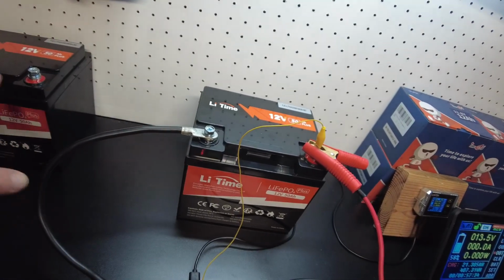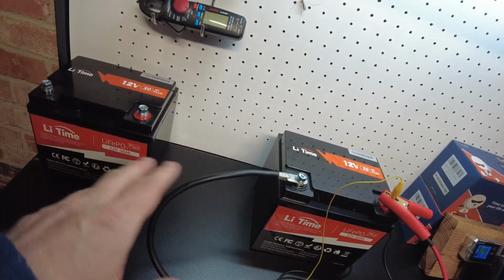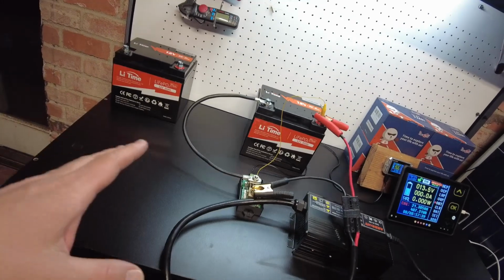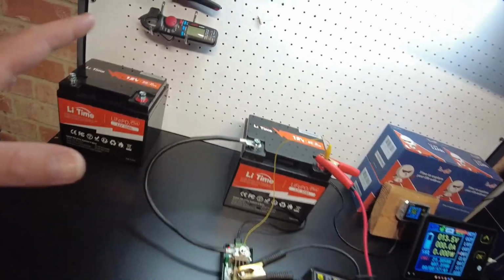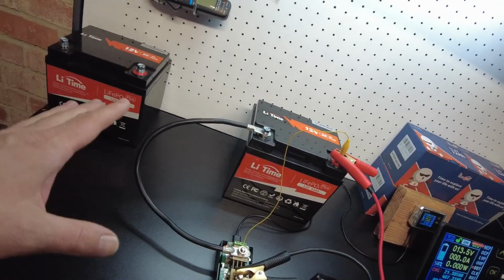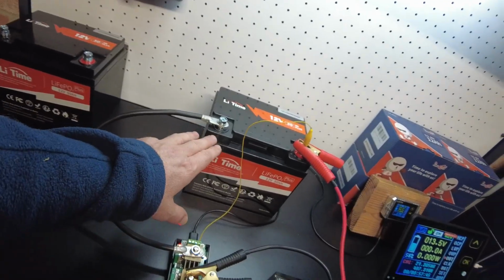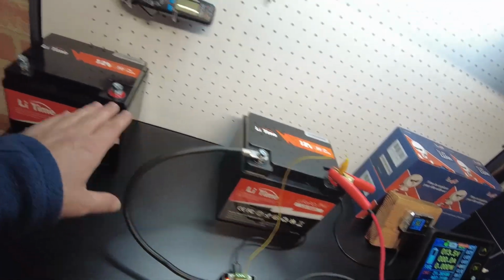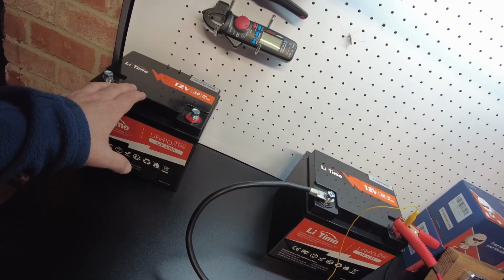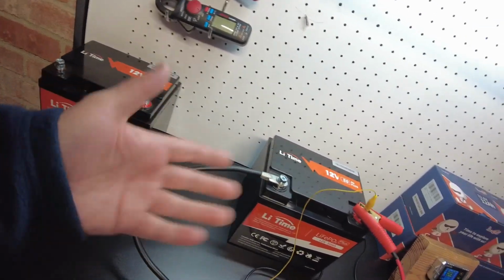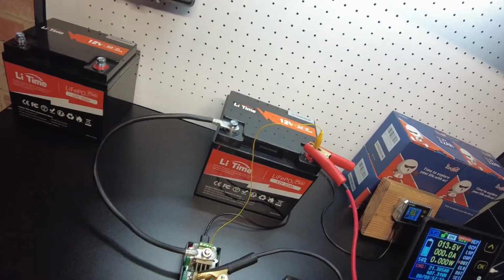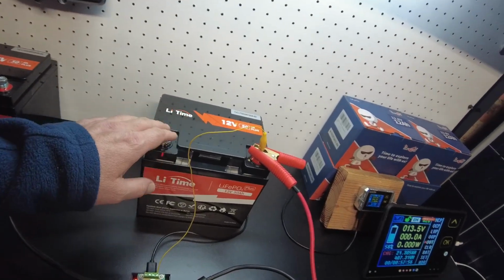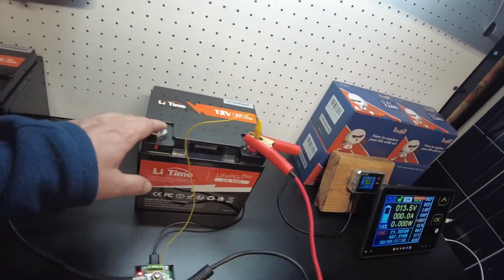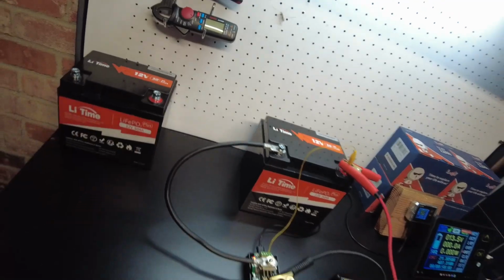So if I had just series these together and started using them in a 24 volt system, the capacity would have been severely diminished because this battery would have been way lower charged than this battery. And it would have never resolved itself. I would have to come in and actually manually charge these batteries individually and top them off to make things work properly.